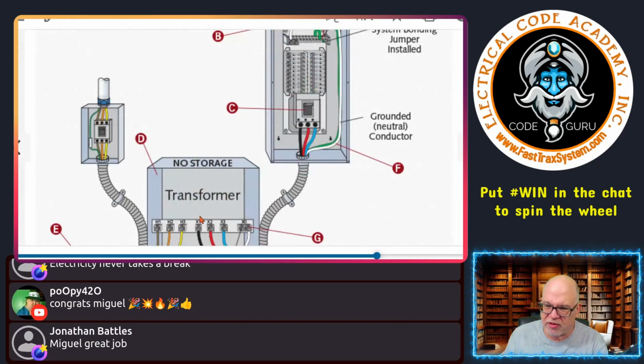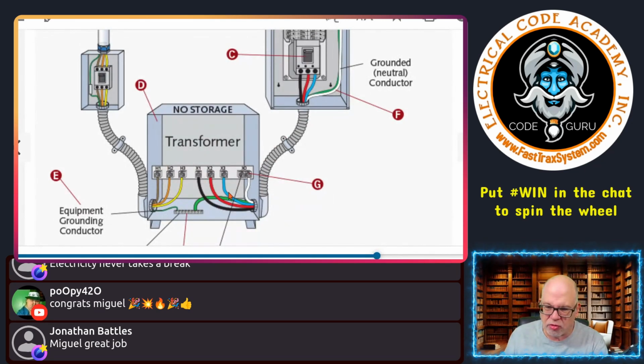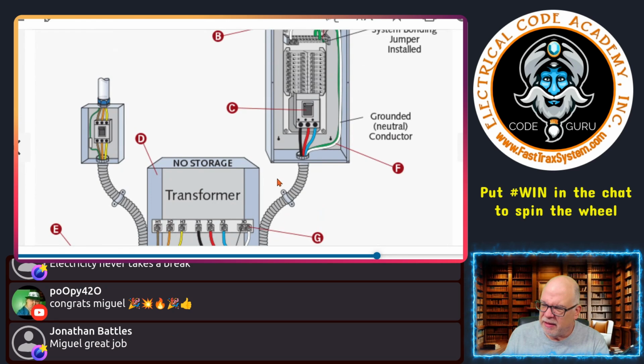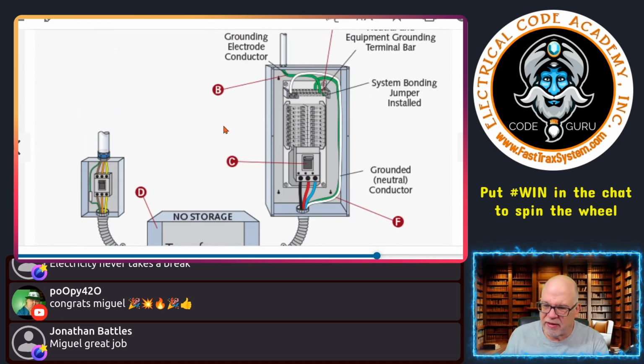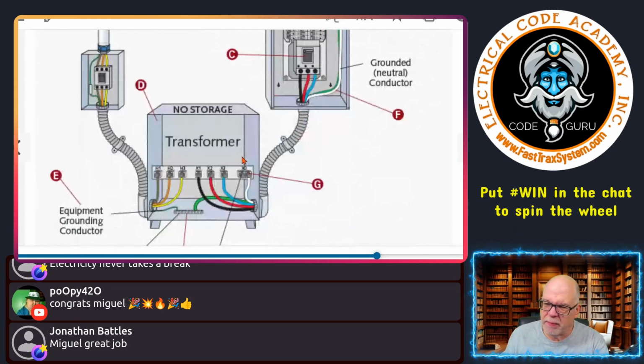Here's a transformer. This is the source. These are called derived conductors because they're not intimate with the primary. The grounding and bonding is, but again, in a separately derived system, the primary conductors and secondary conductors, through the transformer, are not intimate. They're isolated from each other, and so they're not connected together. And anyway, if they were, they would short out. We'd have problems. So here it's chosen to be done here rather than here. It's your choice. Most people do it down here.